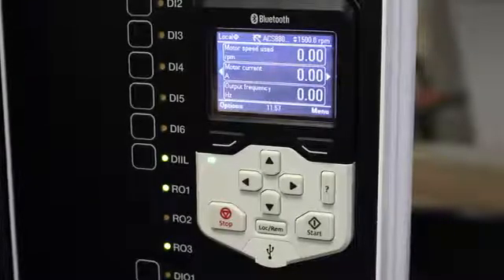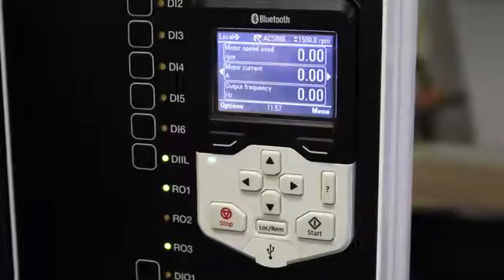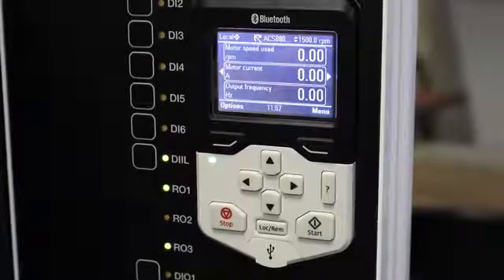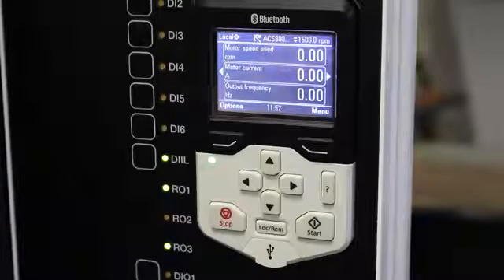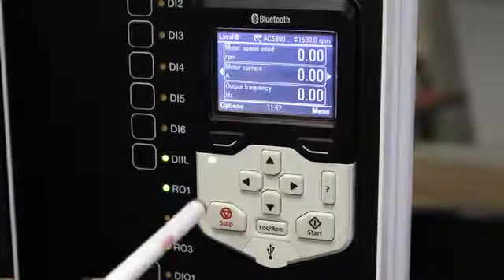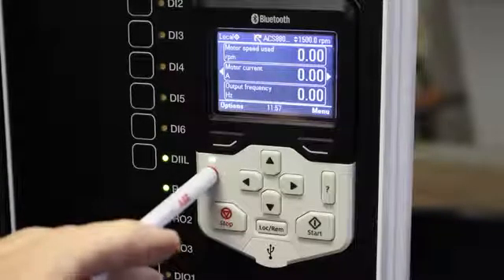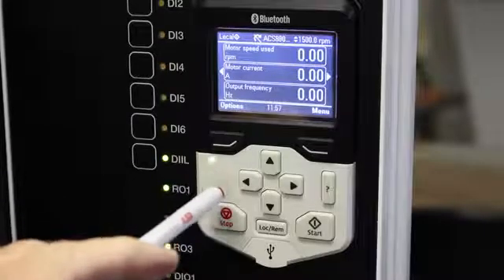Normally when you start your VSD for the first time the basic startup assistant will come up on its own, but this demo unit that I'm using has been commissioned a few times before. To simulate a new VSD I have cleared all parameters back to default, and you will see this little green light flashing over here — it shows me I've got an active alarm.